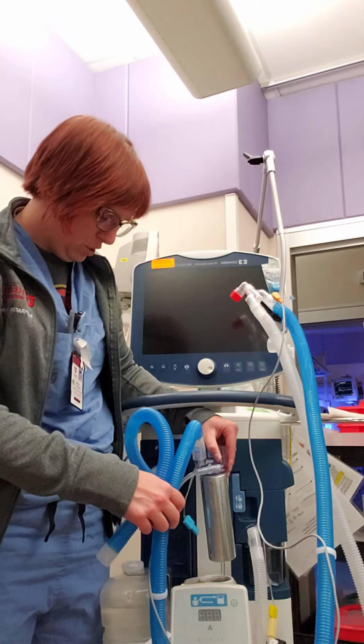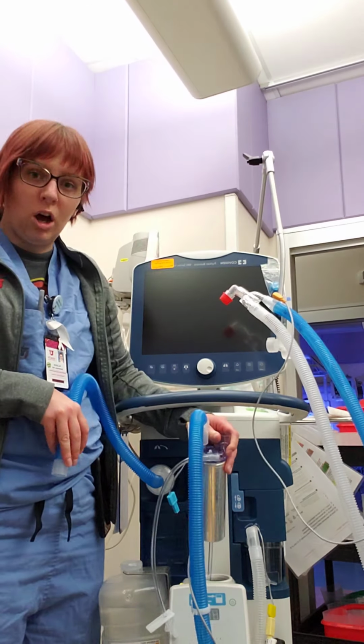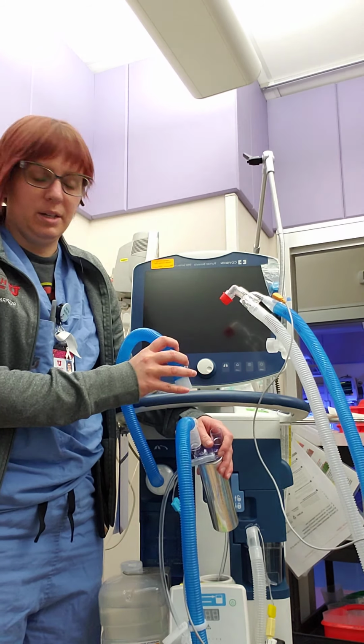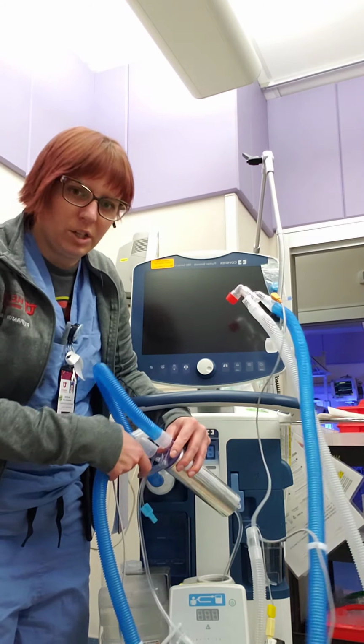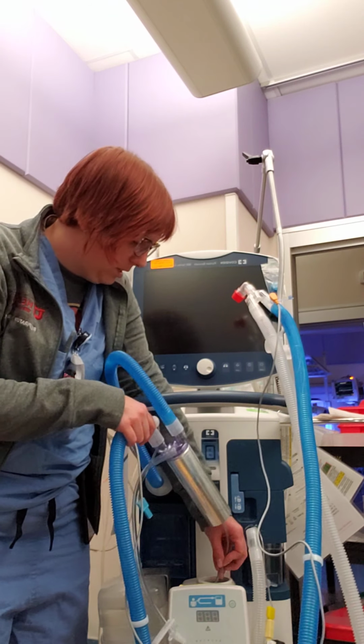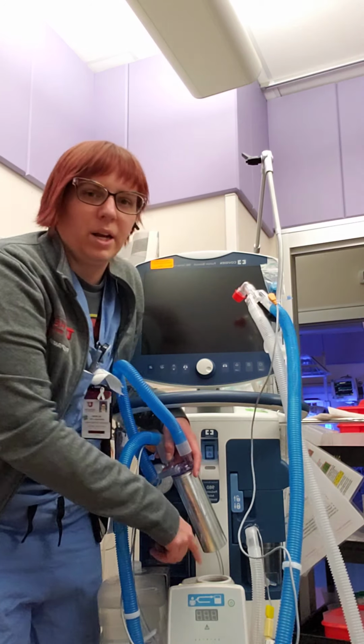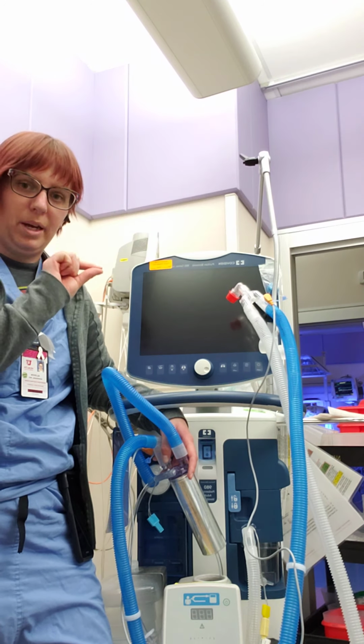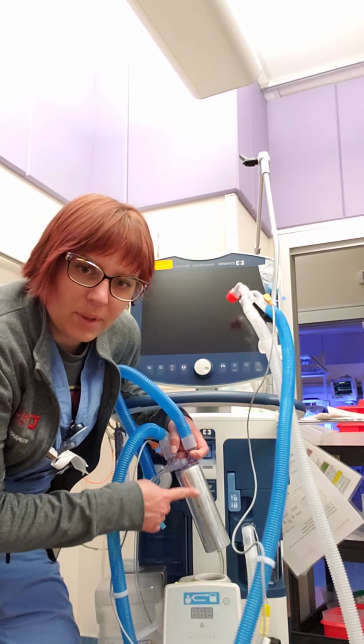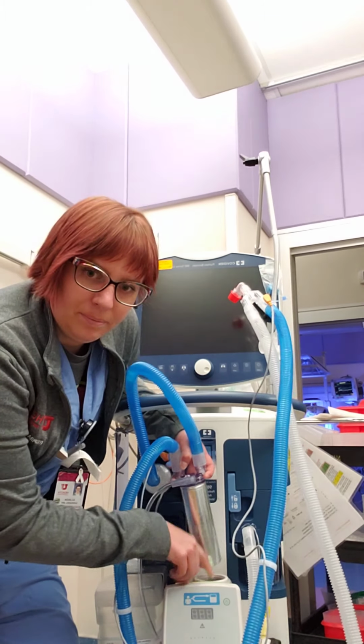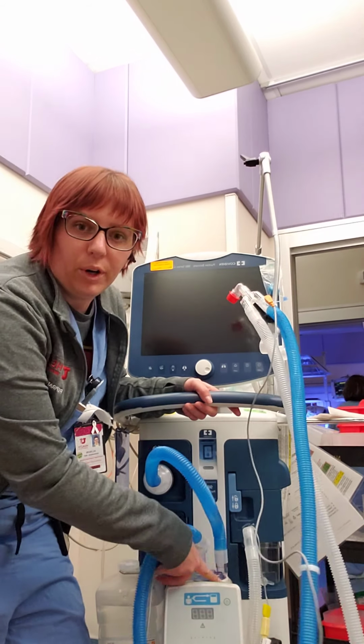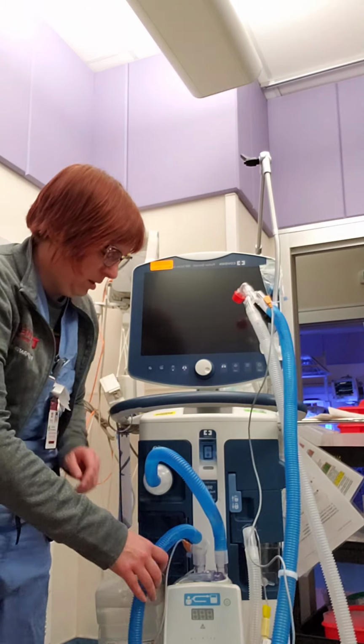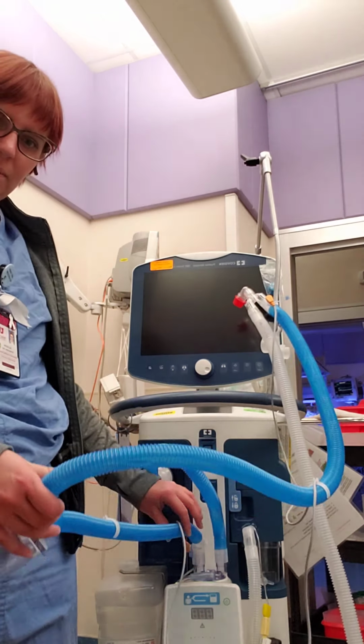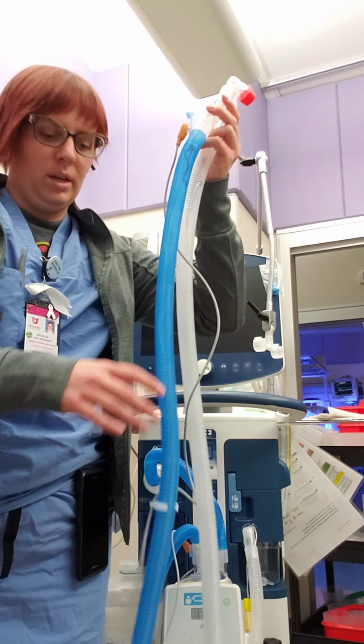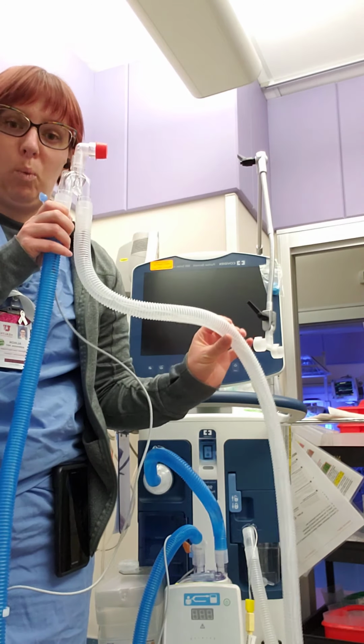These heaters are a little different than the Fisher Paykels that you guys have used before. This is called a concha, and it draws the water up differently to allow for humidity to occur. You stick it to one end of your concha heater, which then slides into the heater here, because how we talked about the metal on metal with the Fisher-Paykel, that's where the heat occurs, is the metal on the metal. Same with the concha. So water goes into here, into this cylinder, and then there's metal in here. We slide in to allow for humidity and heat to occur. From there, we have our inspiratory limb right here, which is blue. Inspiratory limbs are blue, expiratory limbs are white.